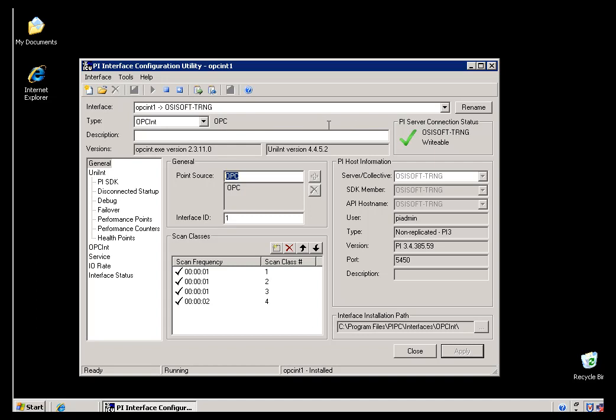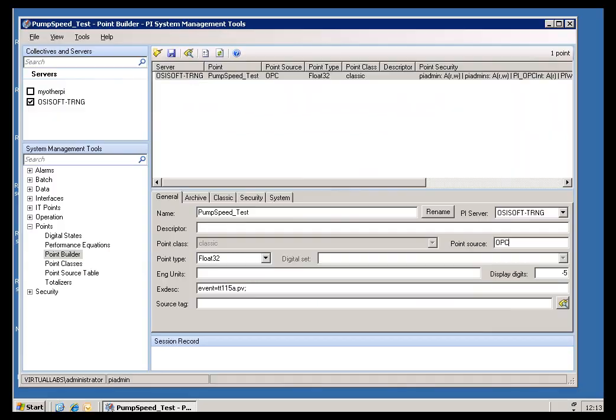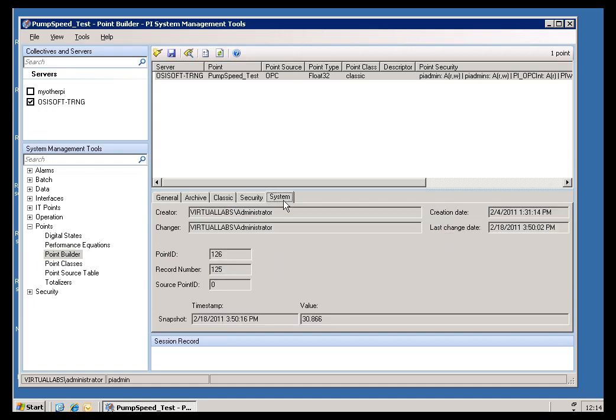Once you've waited for two minutes for your tags to be picked up by the Interface, if you still don't see any values, then there's some troubleshooting tips I can suggest. Here's an example of a tag that I configured, and it's got the right point source, but if I take a look at the System tab, you can see that the value here does have a value, but I know it's a very old value. It's actually much earlier than the 18th of February. I'm looking at a very old piece of data, so there's apparently something going wrong here.